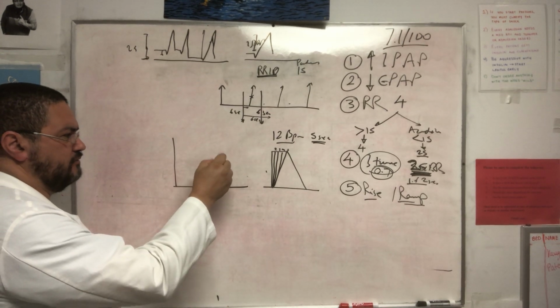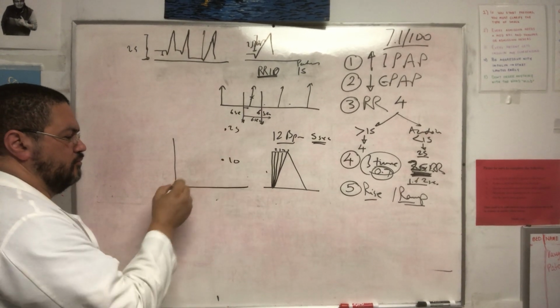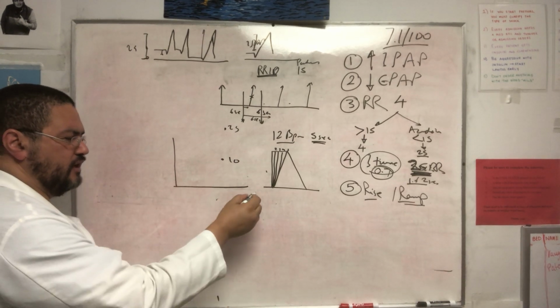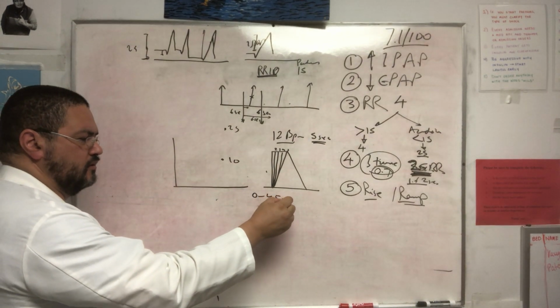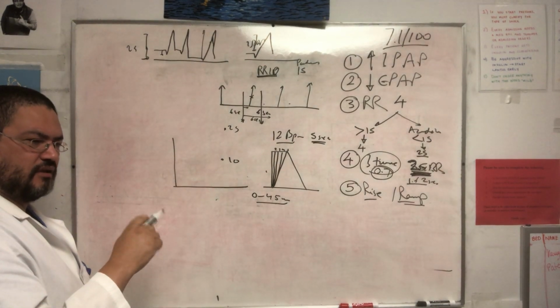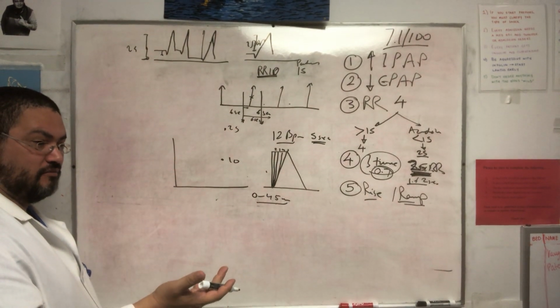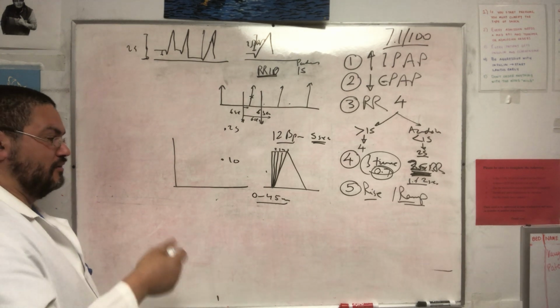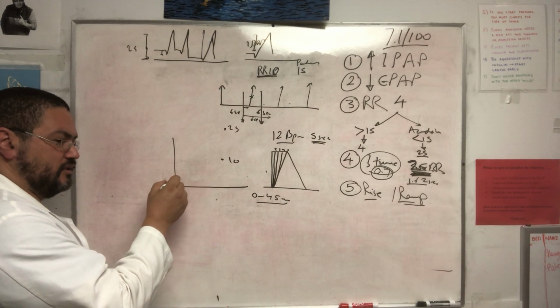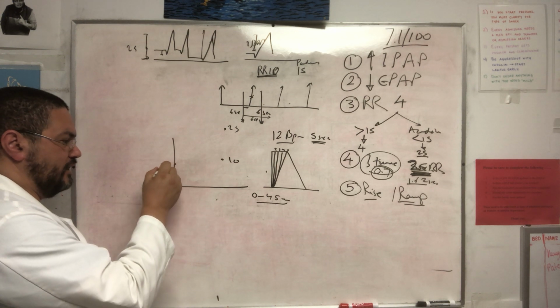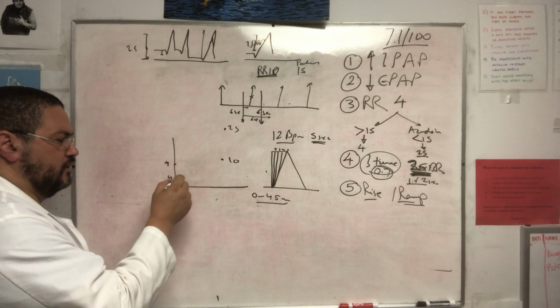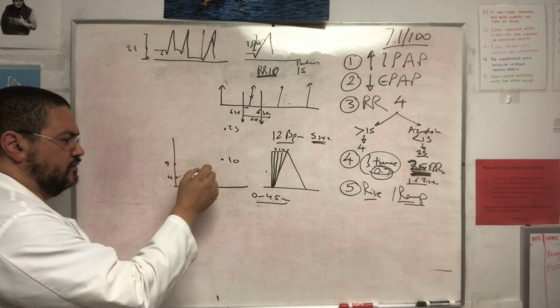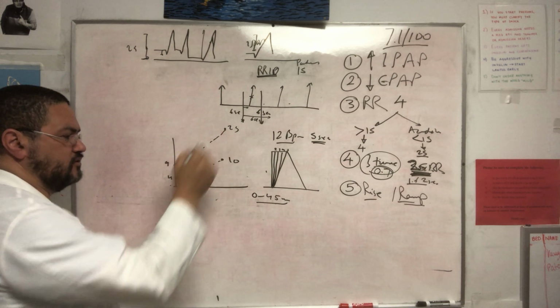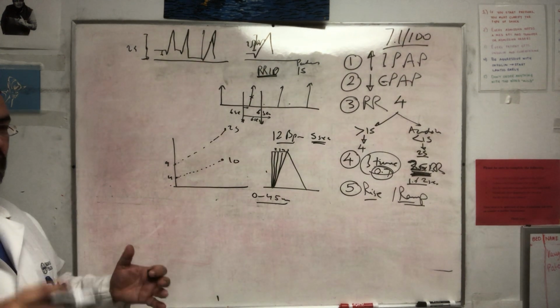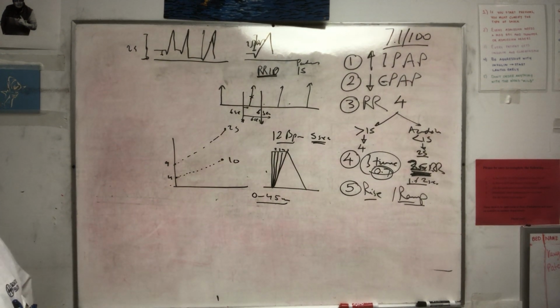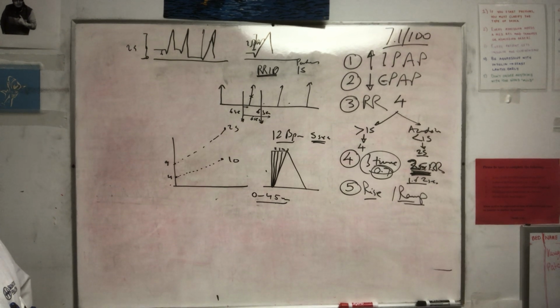You want to have 25/10, right? But if you dial the ramp, you have the option to dial from 0 to 45 minutes. So you're telling the machine, give me those settings that I ordered in 25 minutes or 30 minutes, right? So the machine starts with the smallest settings, like 4, and here is like 9. So 9/4, for example. And then it keeps increasing every minute until it reaches the setting that you want, over time. So the patient actually receives that very well and tolerates it once it reaches there.